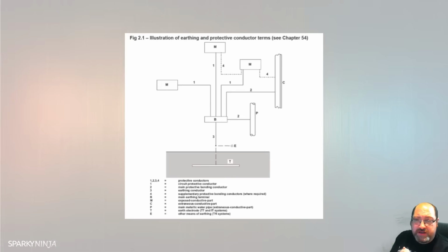An extraneous conductive part is a part of metal equipment that is at zero volt reference potential, so it comes from underneath the ground, normally at the source - water or gas or structural steel like an RSJ - but it introduces a zero volt reference potential within the boundaries of the potential zone of the electrical system. What that means is it brings in zero volts, it needs to be strapped into the bonding. An extraneous conductive part could be water, gas, or structural steel RSJ - it is not part of the electrical system that you distribute. It's known as part of the electrical system because it's zero volt reference to earth, but it's an extraneous conductive part. It's not a conduit, it's not a tray, it's not trunking - those are exposed conductive parts.